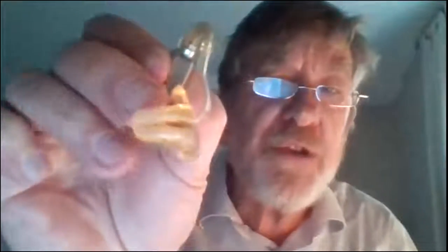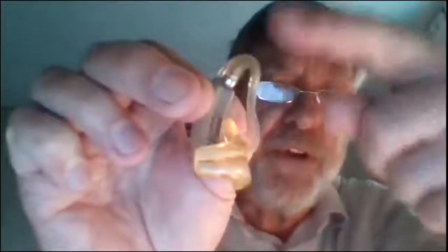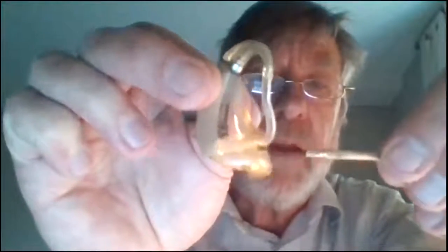Full shell ear mold. Full concha bowl. So this is for someone with a whopper of a hearing loss. Notice there's no vent in there. Here is a Lucite skeleton ear mold. Okay? And the Lucite skeleton ear mold, see how it has two holes? Two pathways. Here's the tube. And the sound goes through the top tunnel. But here is the bottom one. And look at this. I can stick my screwdriver right through it almost. Okay? There you go. That's a vent to stop the occlusion effect.